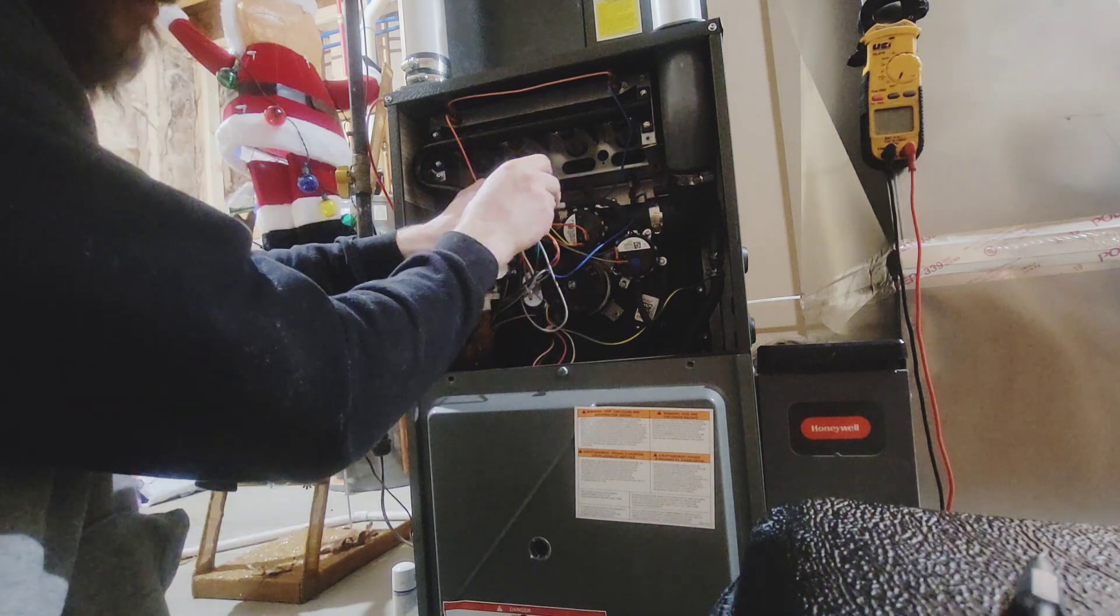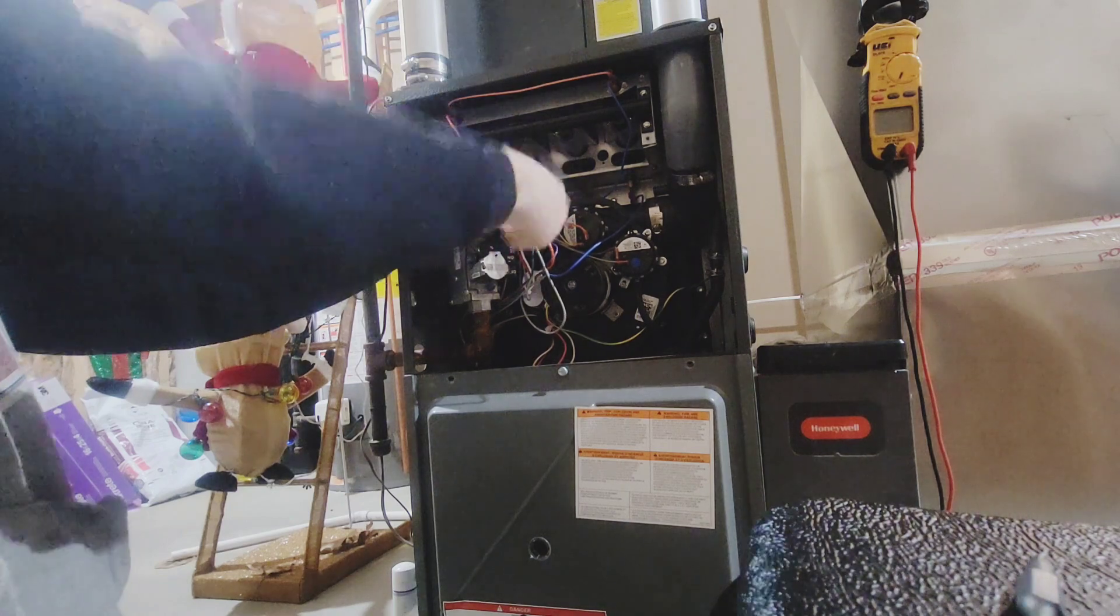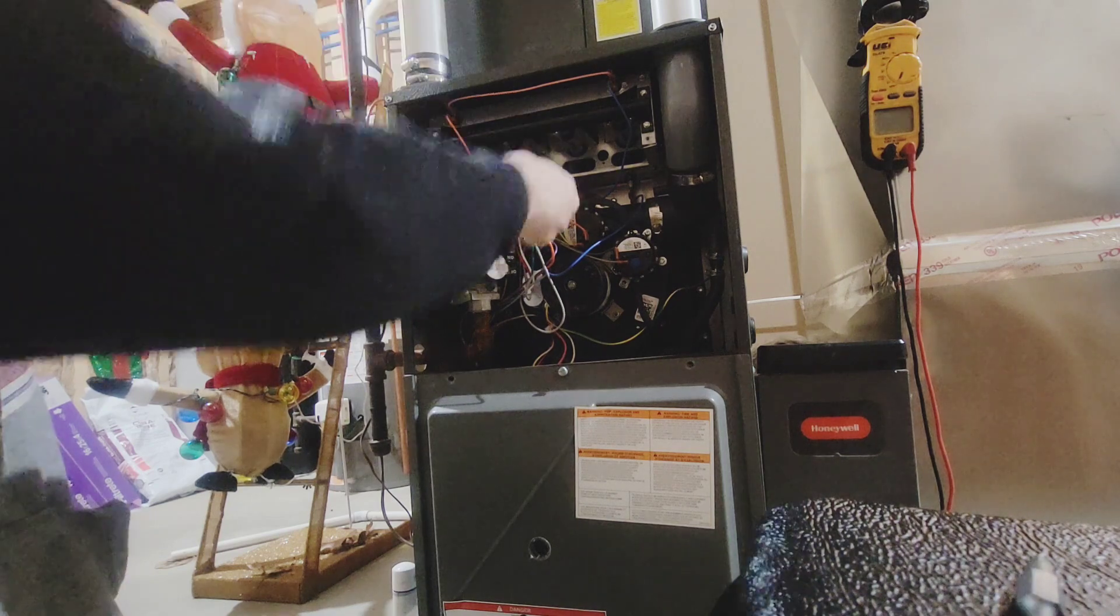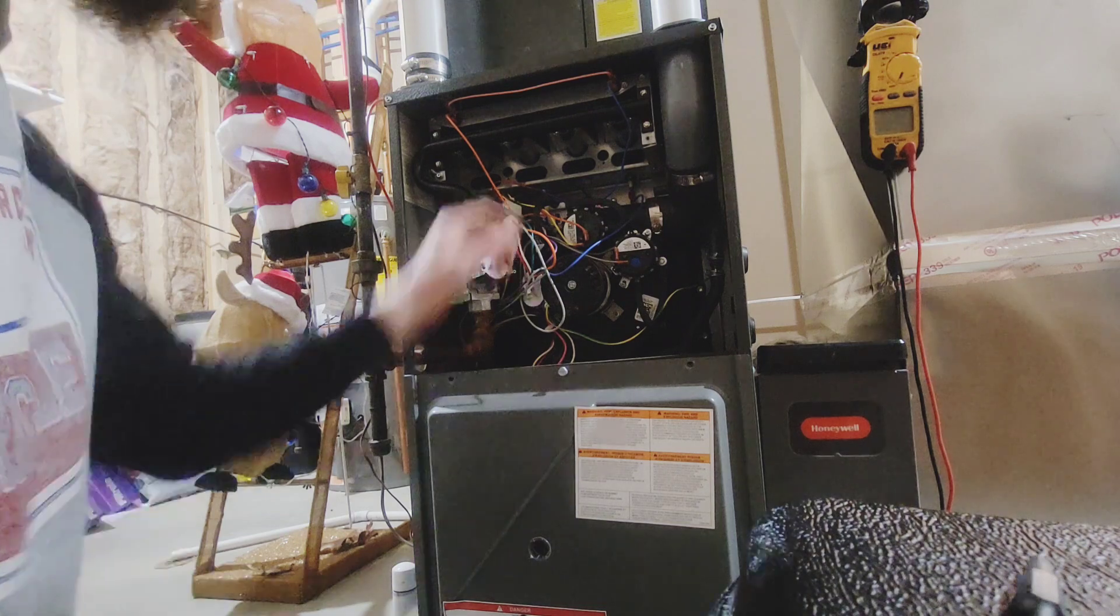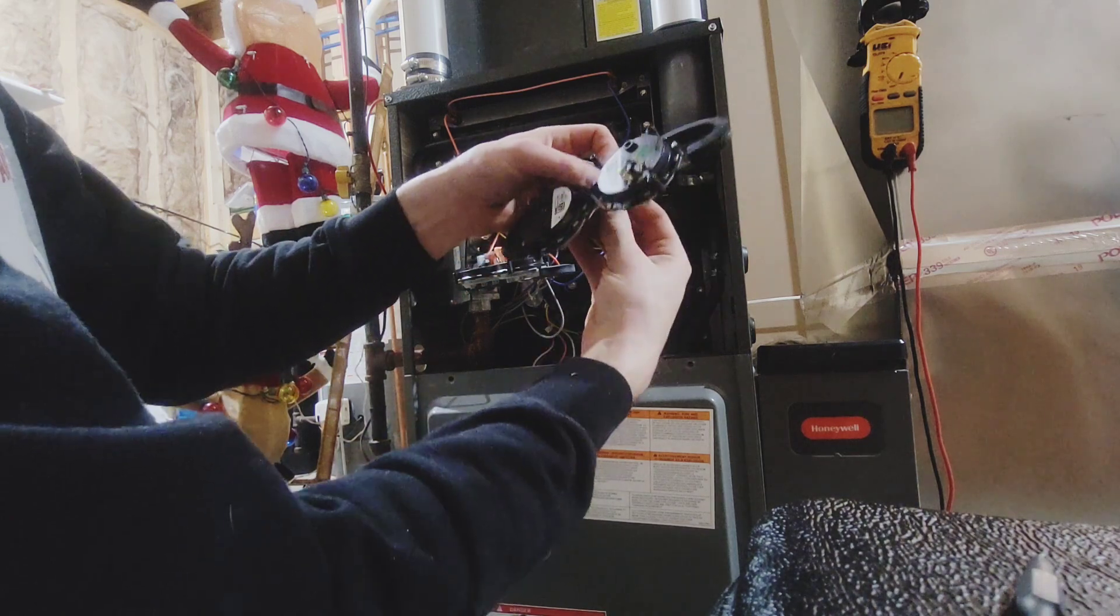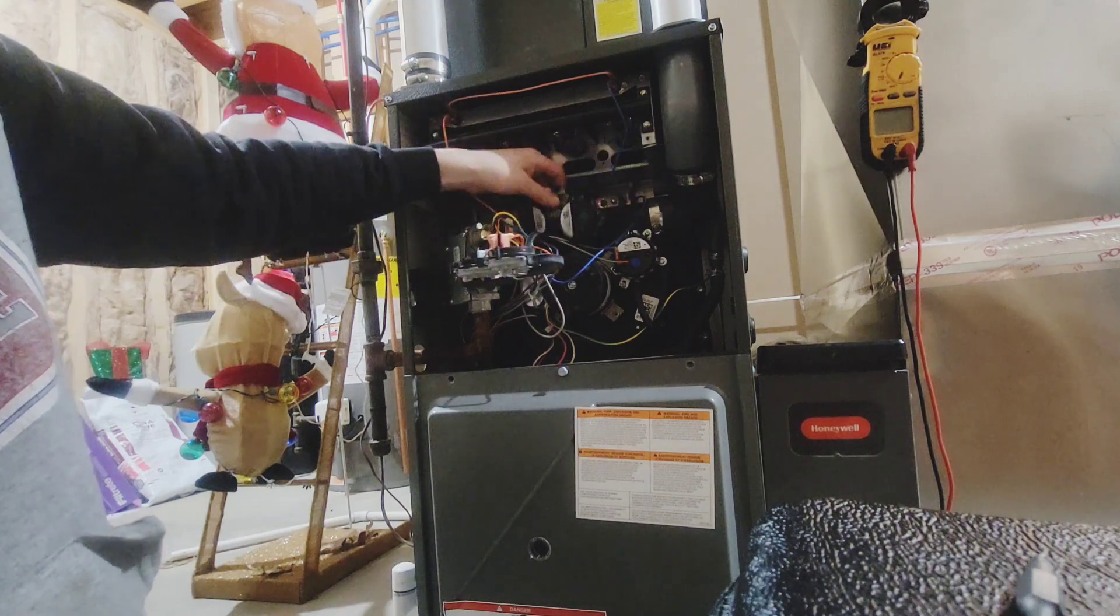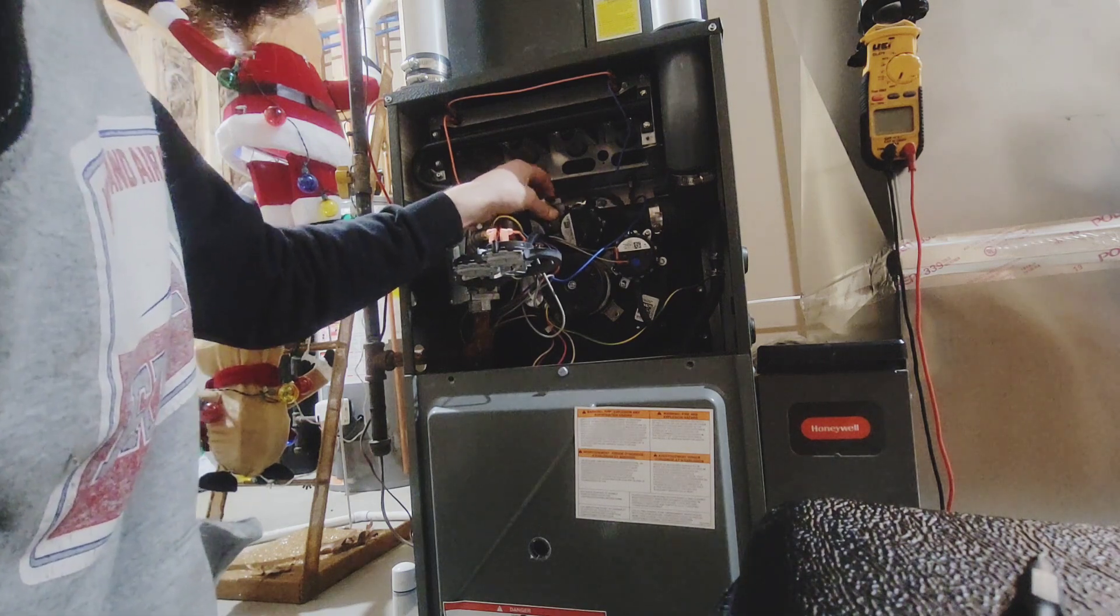So now we're going to take off the main. This is the low fire and high fire pressure switch. Just one screw holding this on, but it's a double. So it has a bracket in between the two pressure switches. You'll see with these, I know it's really hard to tell on the camera. One screw there, but there's a T. So they do share a common vent port. Those kind of just slid right back in there.